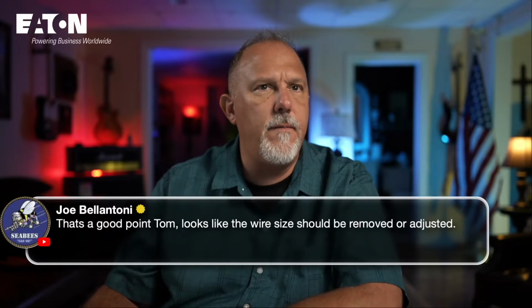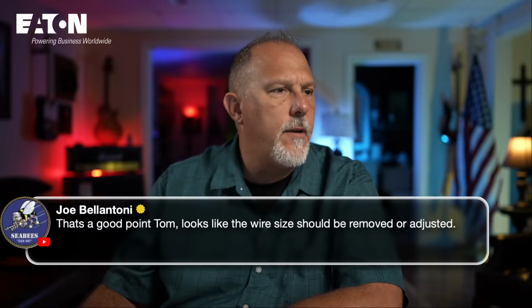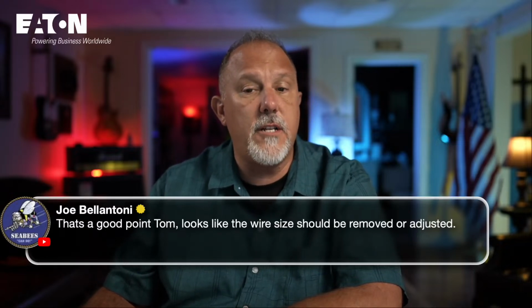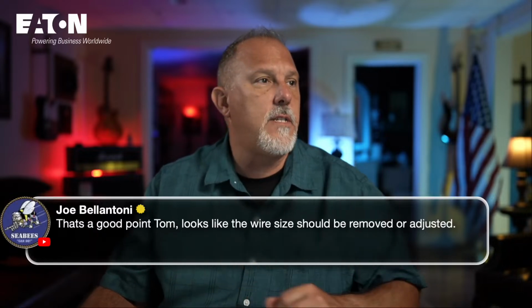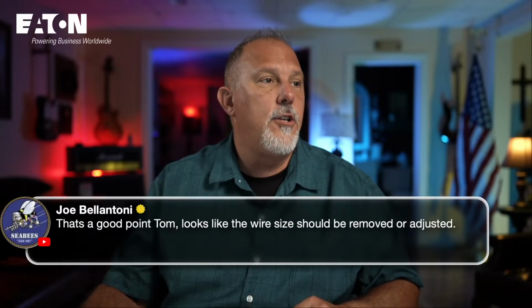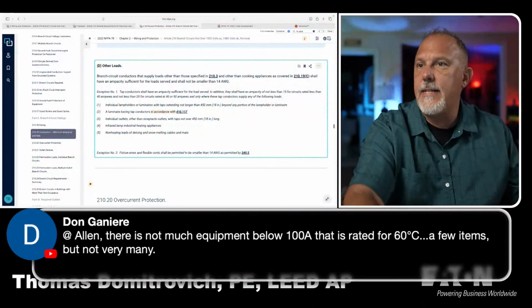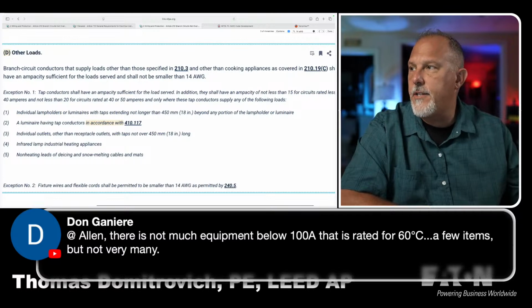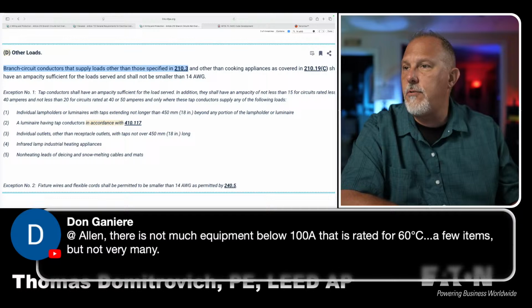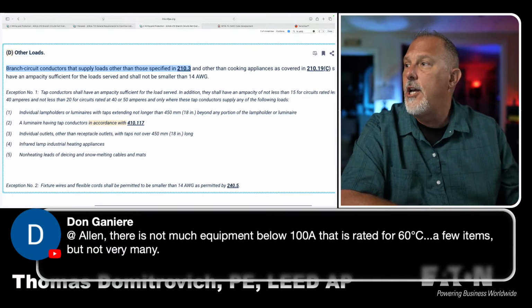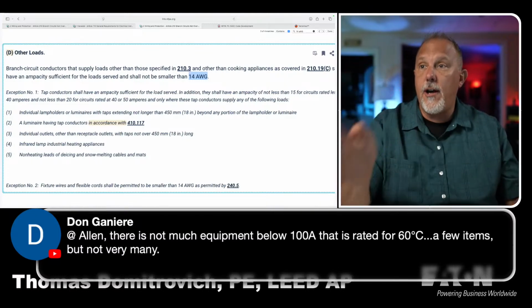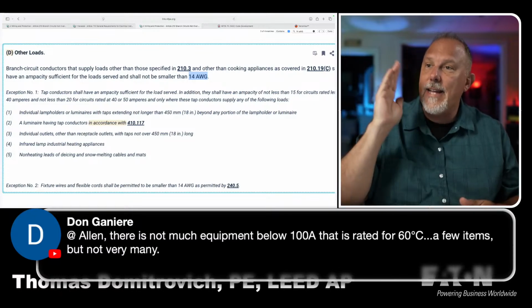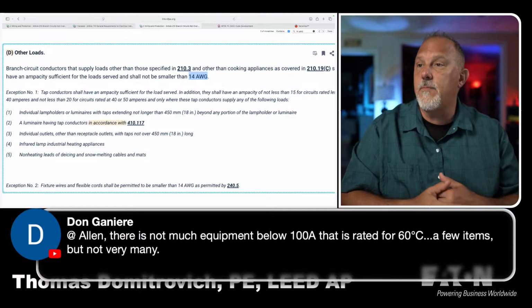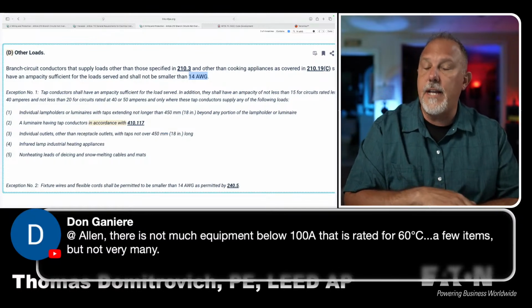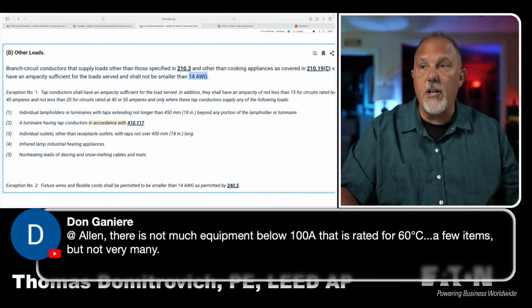All of these are copper only. Other loads. There it is. Branch circuit conductors that supply other loads than those specified in 210.3 and other than cooking appliances. Okay, so this is in 210.19(D). It says branch circuit conductors that supply loads other than those in 210.3 and other than cooking appliances in 210.19(C) shall have an ampacity sufficient for the load served and shall not be smaller than 14 gauge. So now I have a 14 gauge copper, which is a 10 gauge copper clad aluminum. So, at least based upon the 2026, for branch circuits, other loads, I can't be smaller than 14 gauge copper or 10 gauge copper clad aluminum.